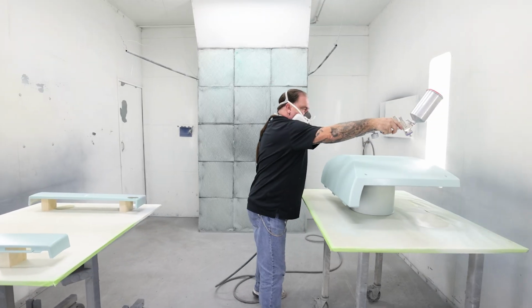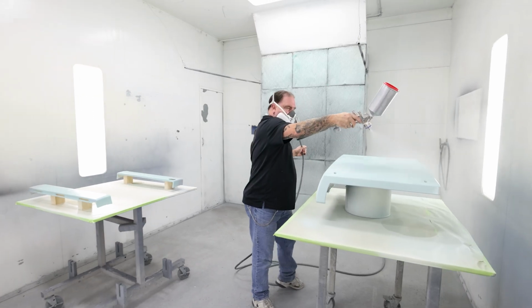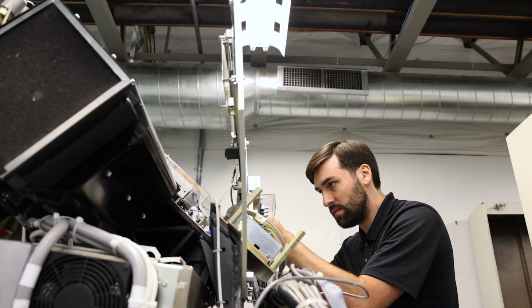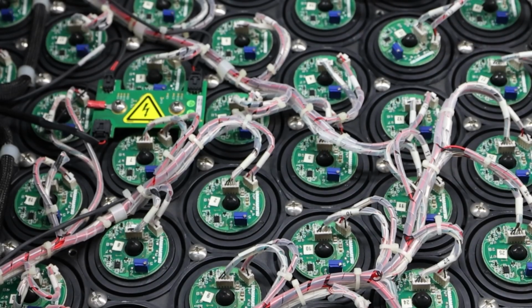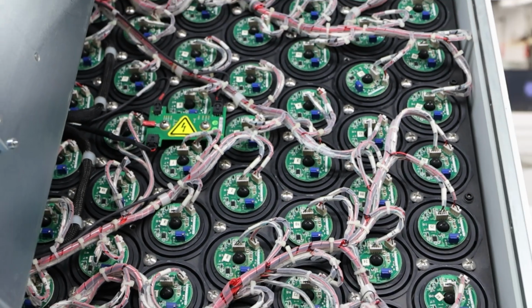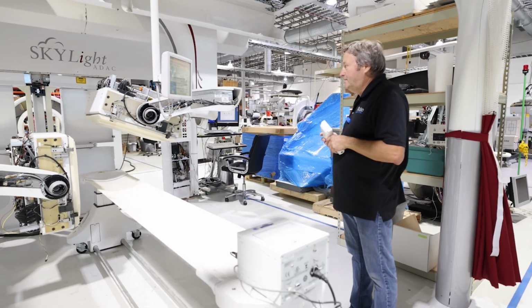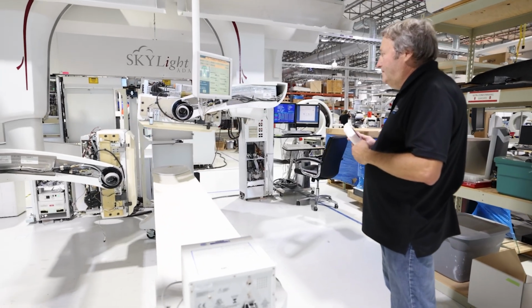Yeah, so for testing we typically use a technetium-99 isotope. It gets put in a syringe and we image from that. It's kind of like a flashlight that shines towards the camera. For refurbishment of these machines, we rework the entire imaging system. So we'll recouple all of the photomultiplier tubes to the crystal so that that's fresh and new. We'll go through all of the mechanical mechanisms and re-grease, clean everything, make sure that the system's fully performing as if it were new.